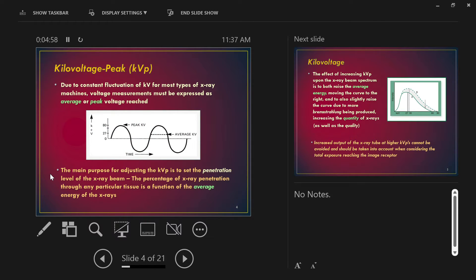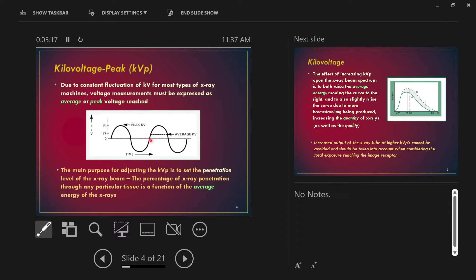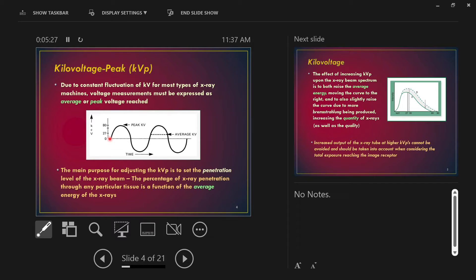This little graph represents the waveform, the alternating current AC current waveform that our devices produce. You know that we rectify alternating current to make it more like direct current. But the point here is to show you X-axis, horizontal axis going through time, vertical axis showing you voltage or energy. As some pulse of electricity begins, you start with zero energy, you go all the way to maximum voltage, peak KV. So if you set 80 KV on your equipment, that's your peak kilovoltage, the peak energy. You won't have any X-rays in the beam that have more than 80 KV if you set 80. That's your beam energy, that's your peak energy rather.